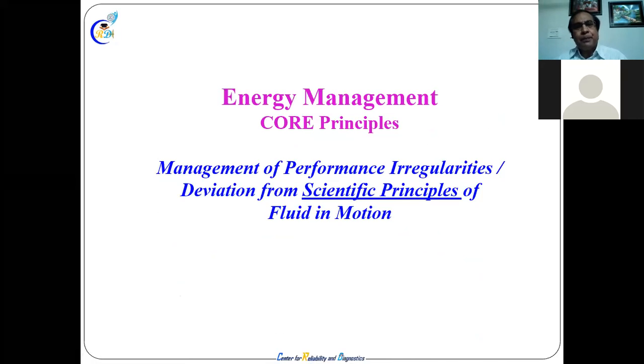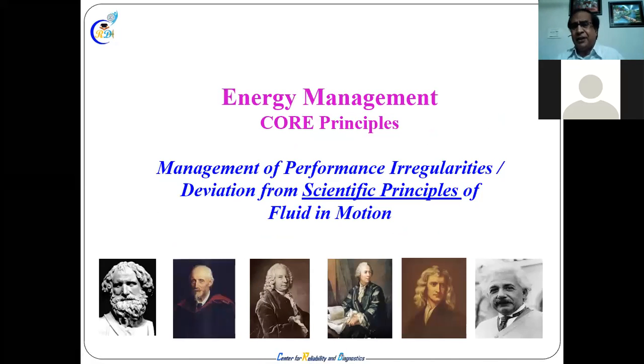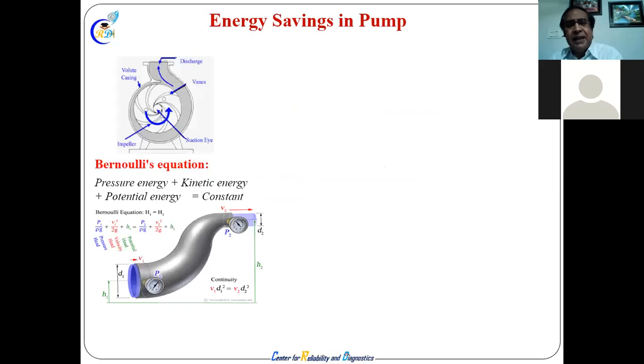So the scientific principles of fluid in motion, all these people have done that. Newton and all these people have done this. So we cannot have any solution as simple as that by any means without attacking performance. Performance is totally based on scientific principle. So that's why the core issue on energy saving in pump, compressor, anywhere is this equation. We are deviating from this equation while operating. And while operating, if you stick to this definition, best efficiency point, we'll never have an energy issue problem.